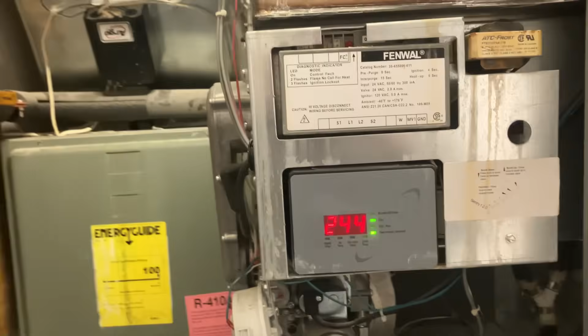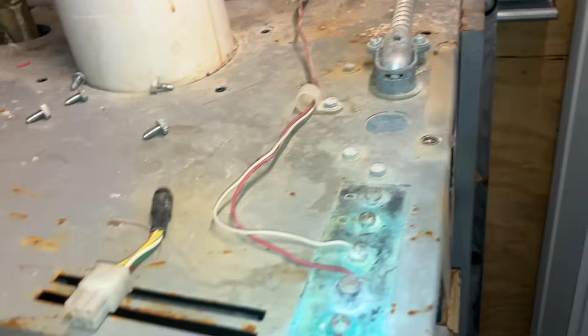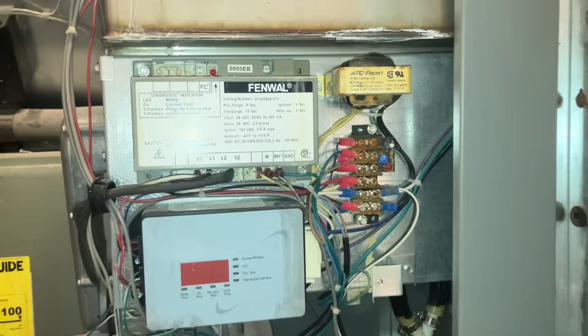All right, got this NTI Trinity Ti200. We have significant water damage to the left rear quadrant of the top of the heat exchanger, not originating from our automatic air valve, but originating from above. Significant corrosion on our low voltage terminals for TT. Luckily, the line voltage compartment is good, but transformer, ignition control module, and most especially that sensor, toast.